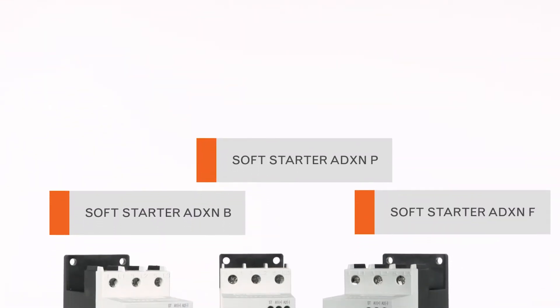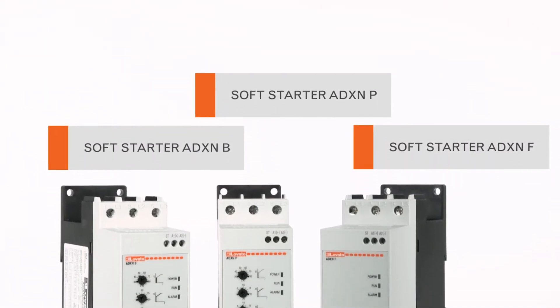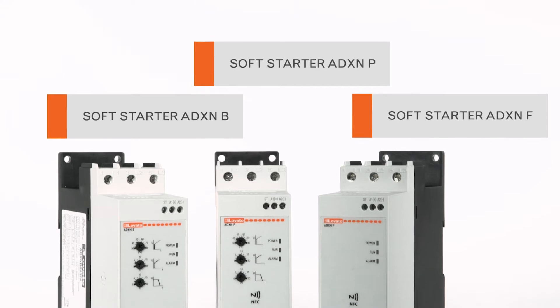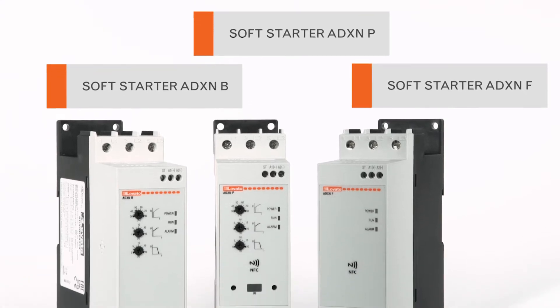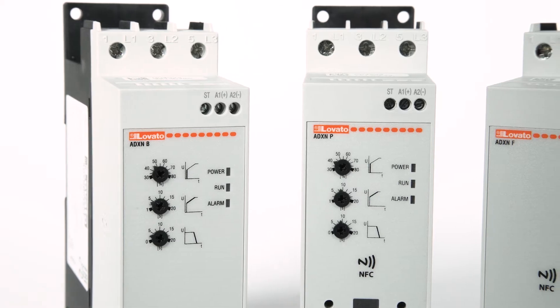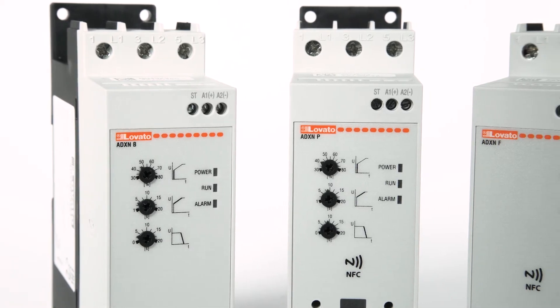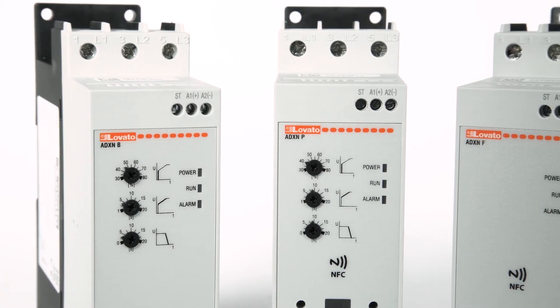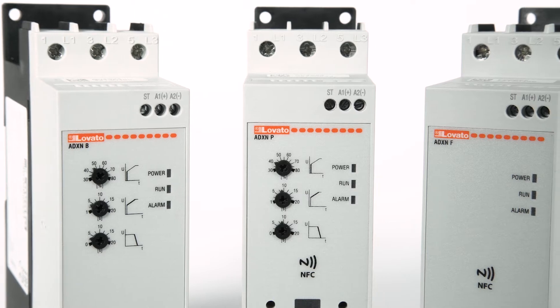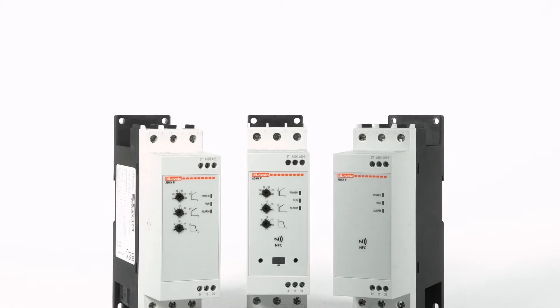The ADXN soft starters control the motor with a voltage ramp that gradually increases from an initial programmable value up to 100% of the line voltage in the set acceleration time. Let's see how to configure the parameters with the front potentiometers.